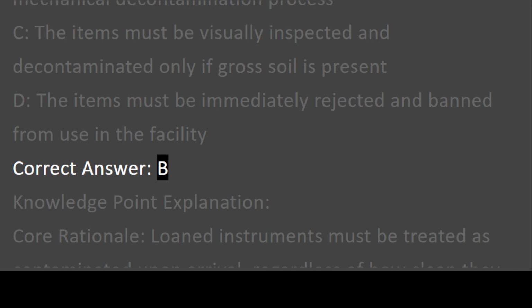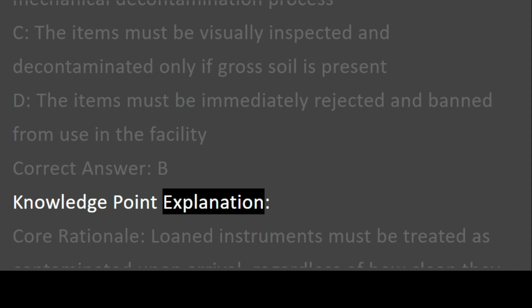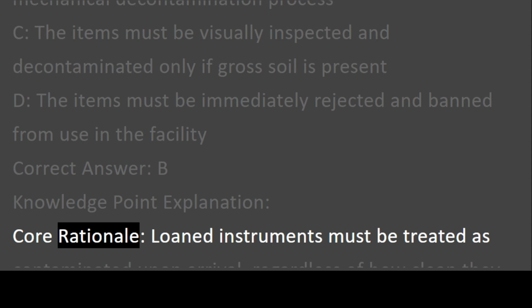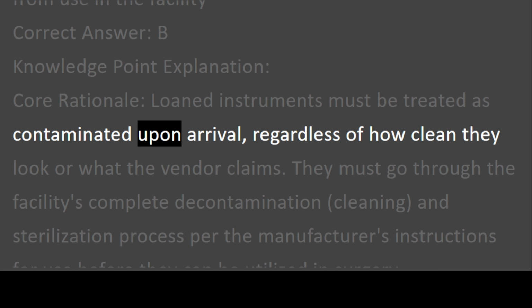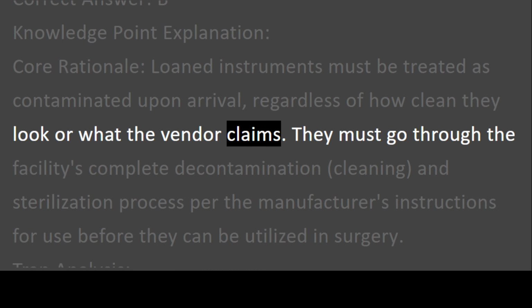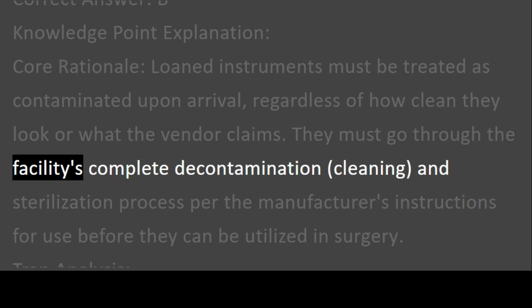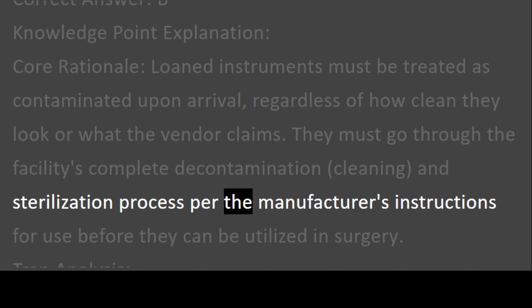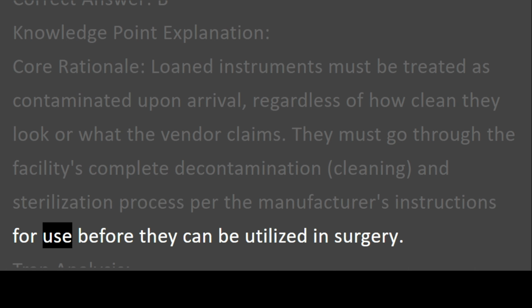Correct answer, B. Knowledge point explanation. Core rationale: loaned instruments must be treated as contaminated upon arrival, regardless of how clean they look or what the vendor claims. They must go through the facility's complete decontamination, cleaning, and sterilization process per the manufacturer's instructions for use before they can be utilized in surgery.